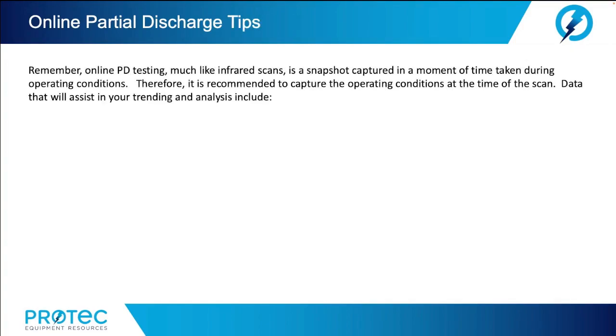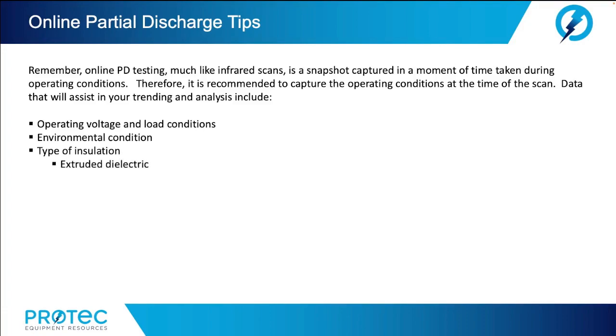Now, remember, online partial discharge testing, much like infrared scans, is a snapshot captured in a moment of time during operating conditions. Therefore, it is recommended to capture the operating conditions at the time of the scan. Data that will assist in your trending and analysis include: what is the operating voltage and the load conditions during your scanning? What are the environmental conditions? What type of insulation are you scanning? Is it an extruded dielectric, a laminated dielectric, or possibly insulating liquids or gas?